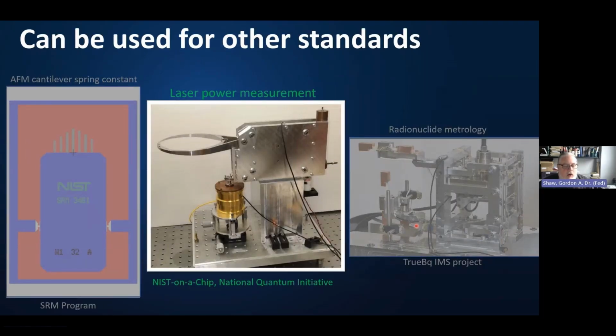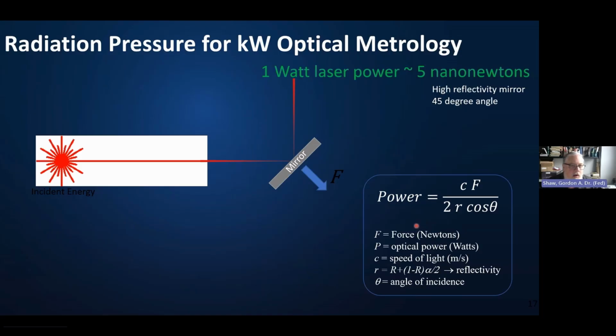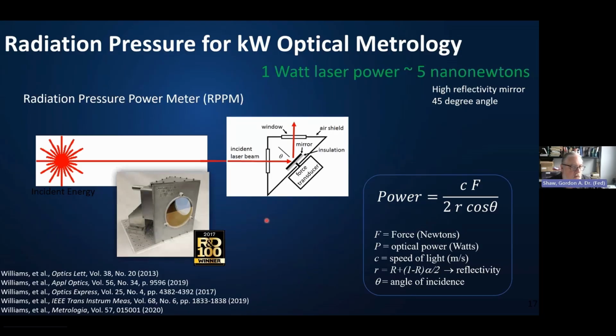Moving on, I want to talk now about another measurement that is of another quantity within the SI, that is laser power, and how we use the electrostatic force balance methods to get a traceable calibration of laser power. In this method, what we do is we use a phenomenon called photon pressure force. When a laser beam reflects from a surface, it generates a force. And this force can be used to calculate laser power using the measured force, the speed of light, and the reflectivity of the mirror. So the idea is that we have a laser source, we reflect off a high reflectivity mirror, and measure the force that is generated from the photon pressure force.